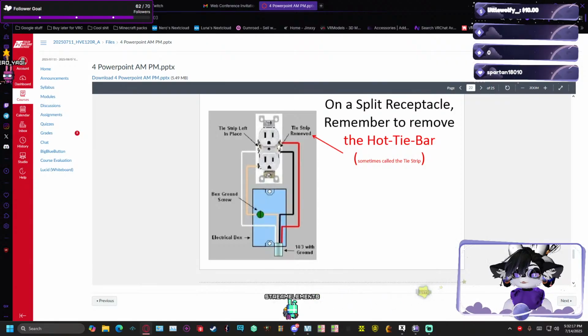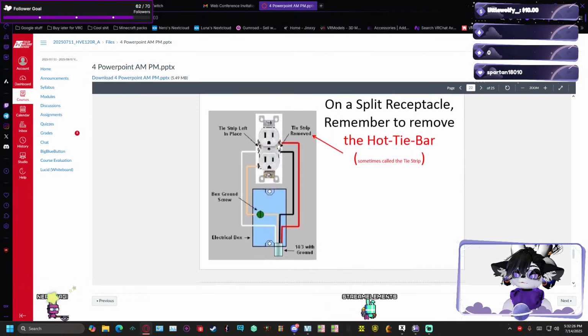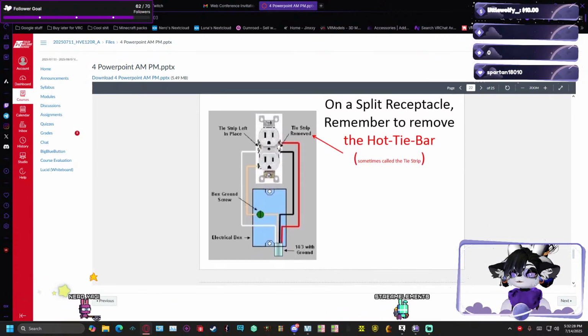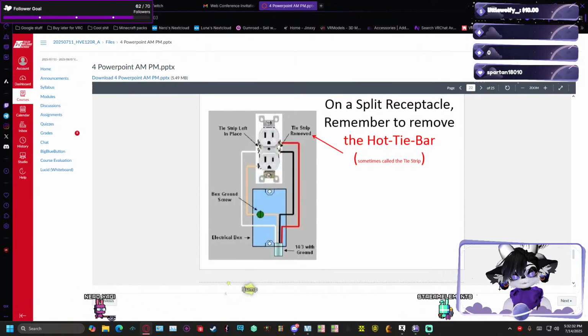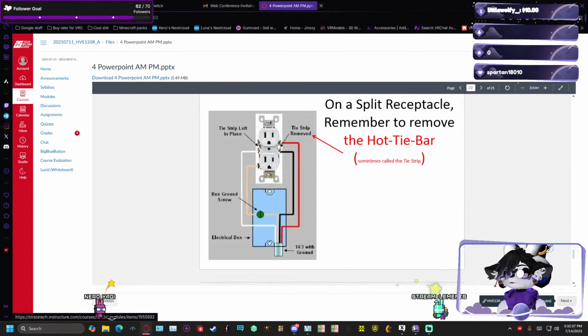So that's a ground. This is the neutral. That's the hot side, and this is also hot, sometimes called a tie strip. On a split receptacle, remember to remove the tie strip, the tab.